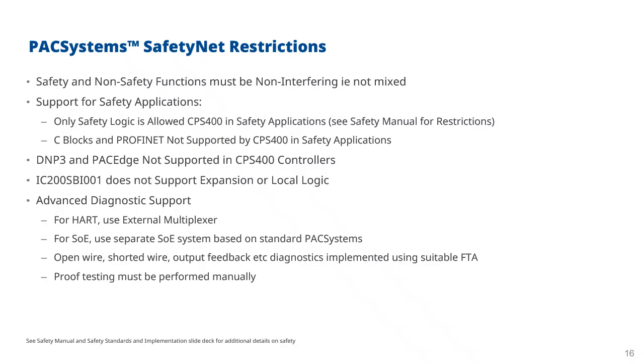As I say, we only support safety applications. So in the CPS 400, there are a few restrictions. We only support the safety logic and a very limited subset of other logic. For example, C blocks are restricted. You can't use C blocks in a CPS 400, and you can't use Profinet in a CPS 400. Now, there is an option if you wanted to use a CPS 400 as a CPE 400, that is possible. You can put it in non-safety mode, and then these restrictions are removed. But when it's in safety mode, you do have these restrictions enforced. I mentioned PAC Edge is not included. DNP3 is also not included in the CPS 400.